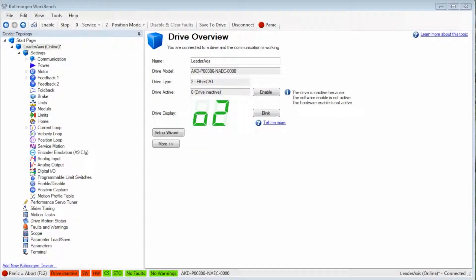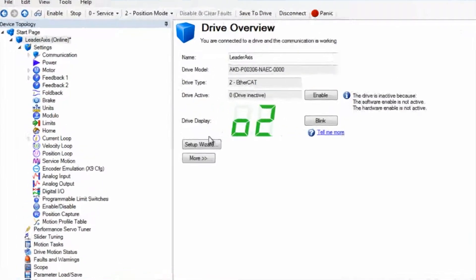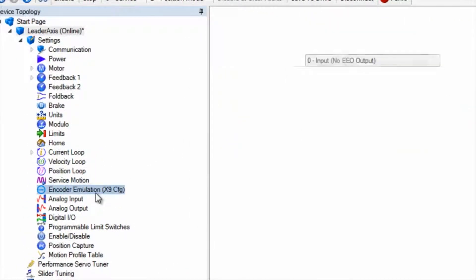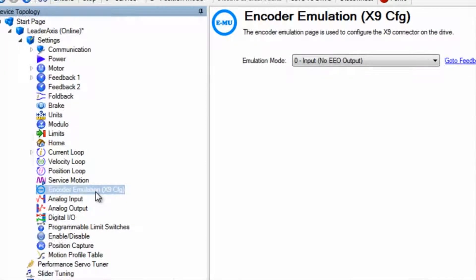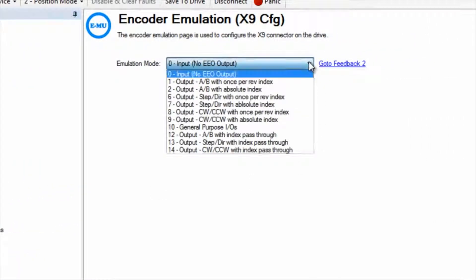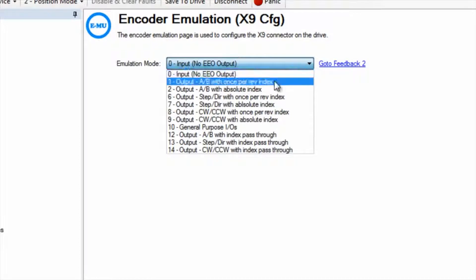When the AKD is applied as the leader we can set up the output for connector X9 using the Workbench software. In this demonstration I have set emulated encoder mode to type one output and AB channels with once per rev index pulse. This will simulate an incremental encoder.